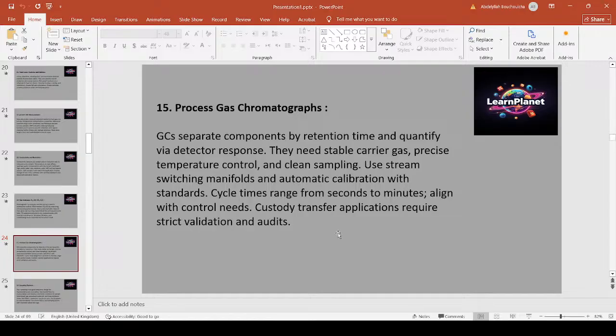Process gas chromatographs, GC. GCs separate components by retention time and quantify via detector response. They need stable carrier gas, precise temperature control, and clean sample streams. Use stream switching manifolds and automatic calibration with standards. Cycle times range from seconds to minutes, so align with control needs. Custody transfer applications require strict validation and audits.